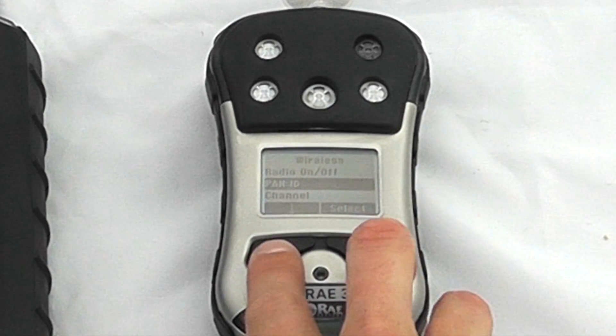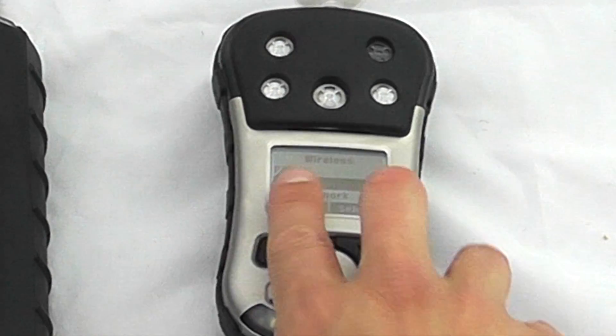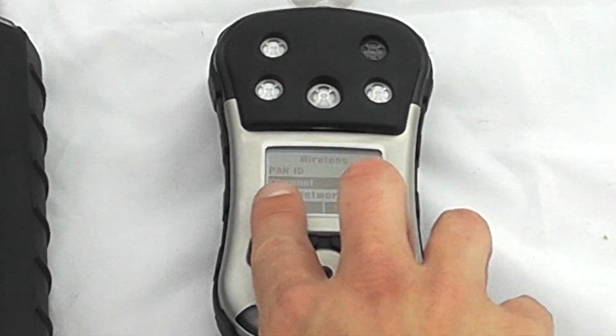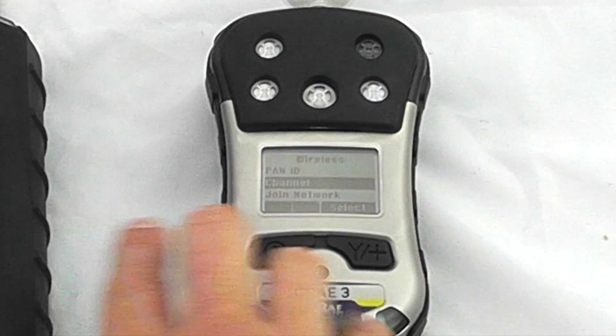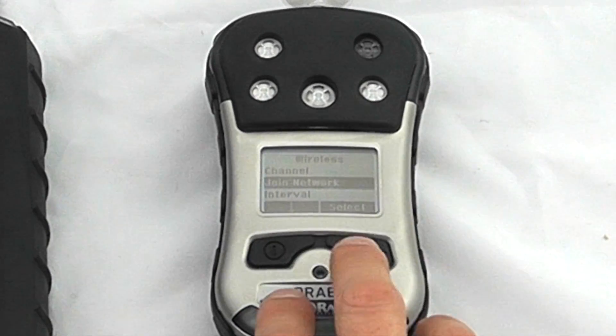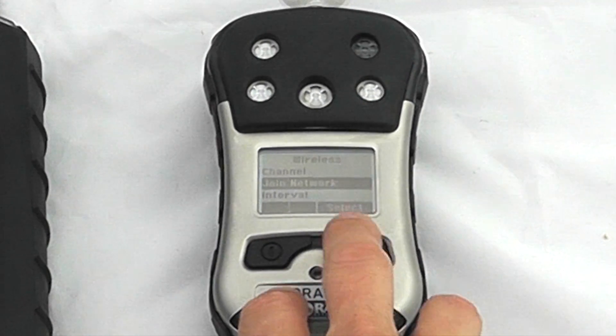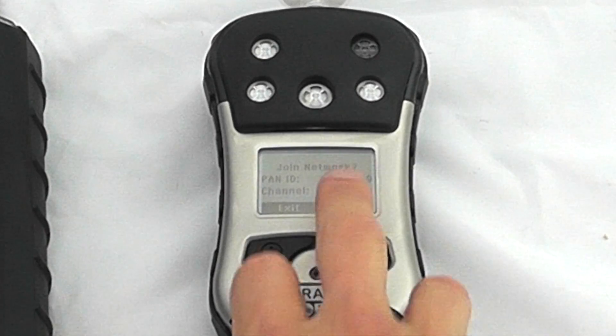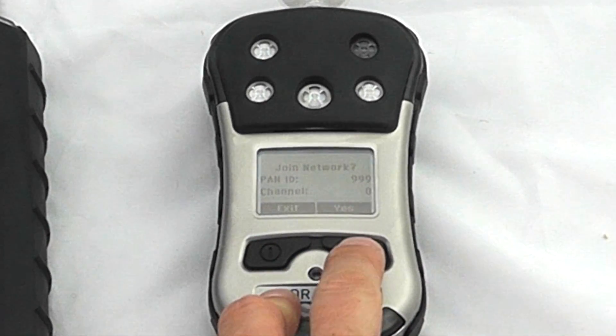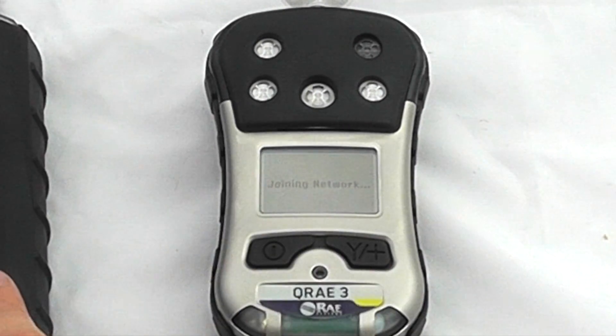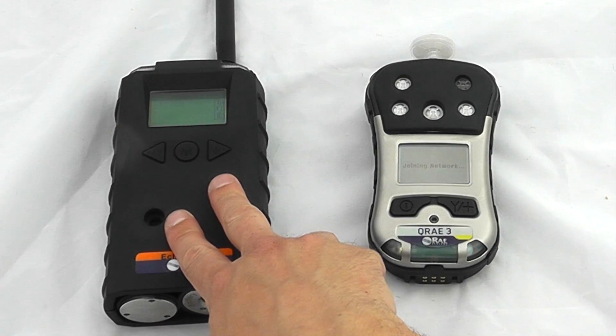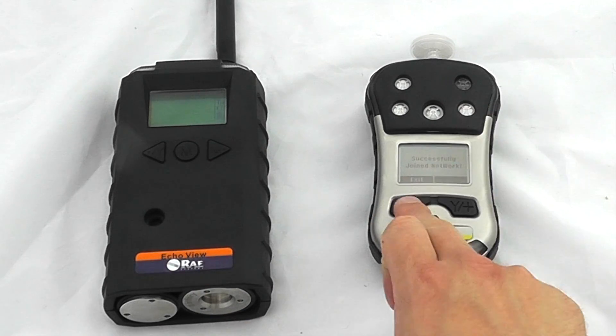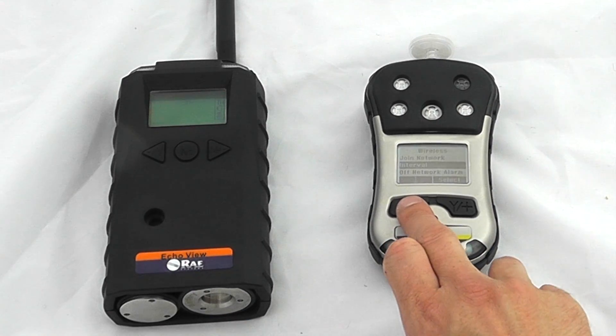Make sure the PAN ID and channels match. My PAN ID is set to 999 and my channel is zero, matching this device. To join the network initially, hit select. The instrument will confirm whether to join—yes, we do. It will then join the network. A closed-loop network is limited to eight different devices. We can see this has successfully joined.